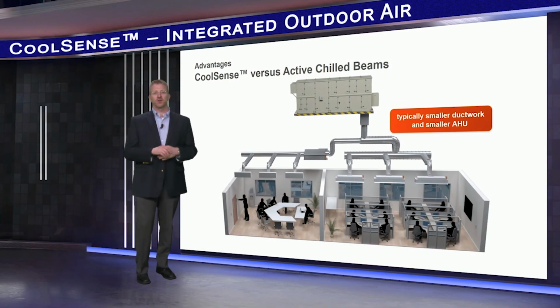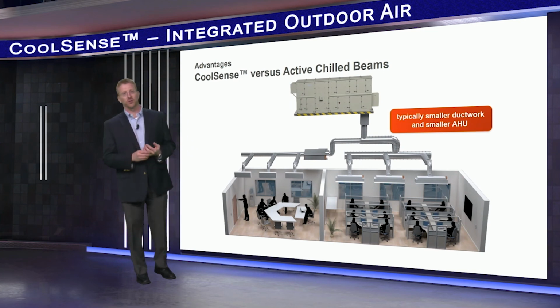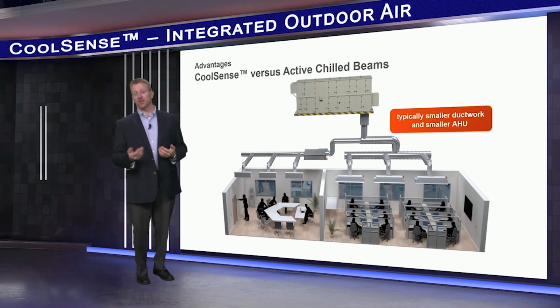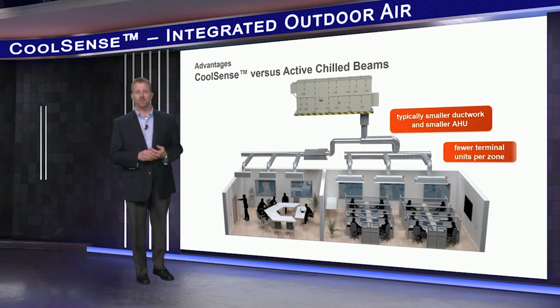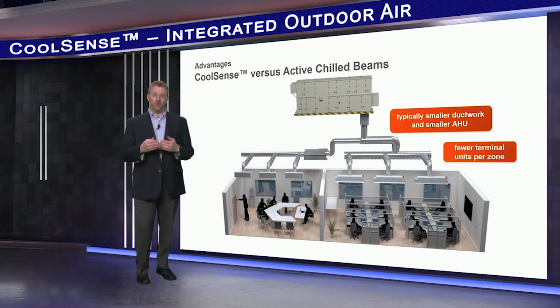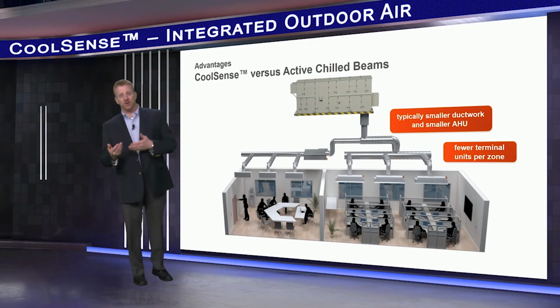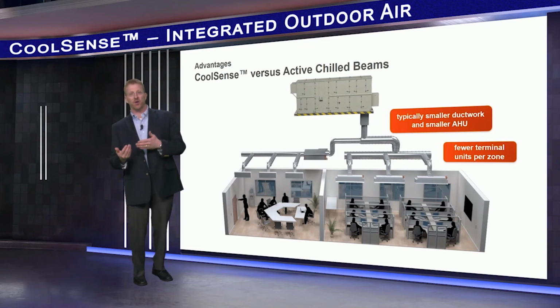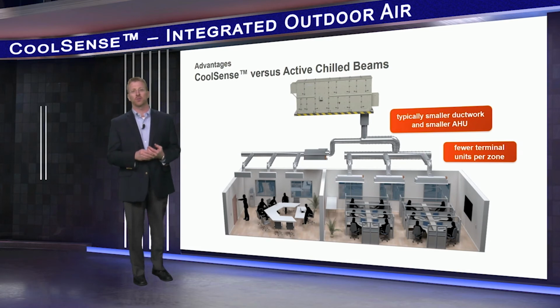We've done previous work in this area and have listed the Trane Engineers newsletter on active chill beam systems in the bibliography. Also, there are typically fewer terminal units, as a CoolSense system uses one terminal unit per zone in most cases. The terminal fan allows for higher cooling capacities per area of coil surface than using induction in chill beams. In contrast, typically multiple chilled beams are required per zone.